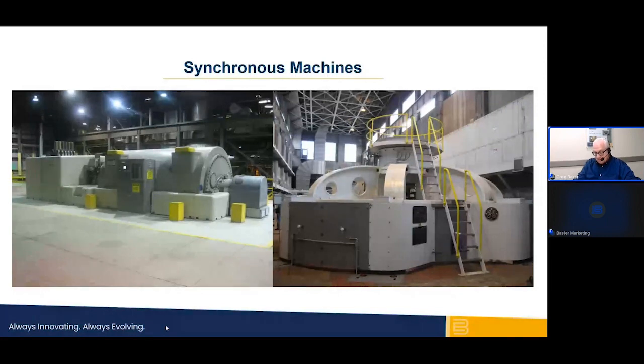The magnetic connection made between the rotor and stator establishes a strong link that will impart more of the mechanical torque. The stators, also known as armatures, of an induction motor, a wound rotor motor, or a synchronous motor are all the same. The difference is in the rotor. While the rotor is sufficiently excited, the machine remains locked in for all loads. Next slide, please.